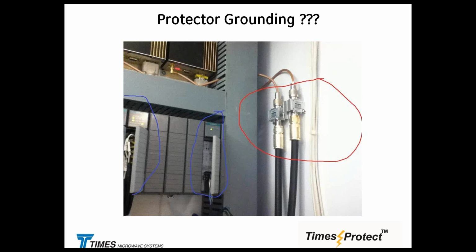The protectors are not grounded at all. They are sitting very, very happy. They are not being bothered by anything, and the guy keeps blowing his channel banks. So I said, hey, we're going to do a very inexpensive fix. Go to the Home Depot, get yourself a piece of copper, a piece of aluminum, ground this. We added a very nice strap. I also advised him to capture. He didn't have grounding kits on the water tower at all. He didn't have grounding kits for the coax shields as they came into the building. So basically we fixed it.